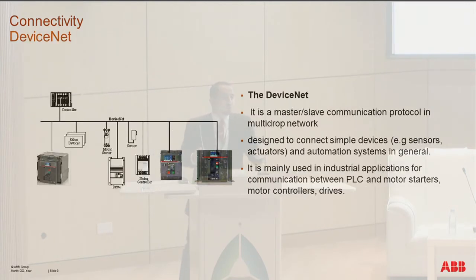The third protocol that we can provide also is DeviceNet. DeviceNet is also used for supervision and controlling the system, like Profibus, but Profibus has a higher data baud rate than DeviceNet. Its application is mainly used for communication between a PLC and the motor starters and motor controllers in factory automation. It's integrated in the ABB Emax2 air circuit breakers, while in the molded-case circuit breakers, it needs an external converter. So we can also provide that.